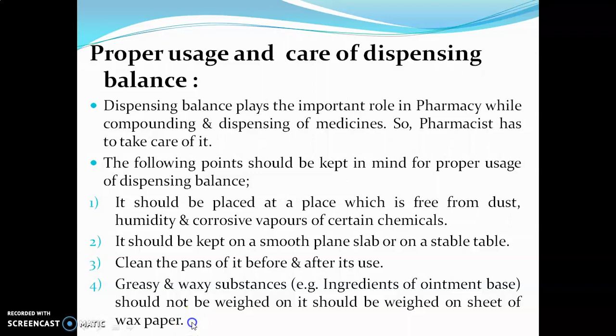Third, clean the pans before and after use. Fourth, greasy and waxy substances, for example ingredients of the ointment base, should not be weighed on it directly, but should be weighed on a sheet of wax paper. Fifth, always use a spatula to transfer material from bulk packing to the pan. Sixth, the drawer of the balance is closed while weighing. Seventh, weights should be transferred with the forceps. Eighth, after using the balance, it should be cleaned with a soft cloth or brush. Ninth, when the balance is not in use, it should be cleaned and covered with the balance cover.